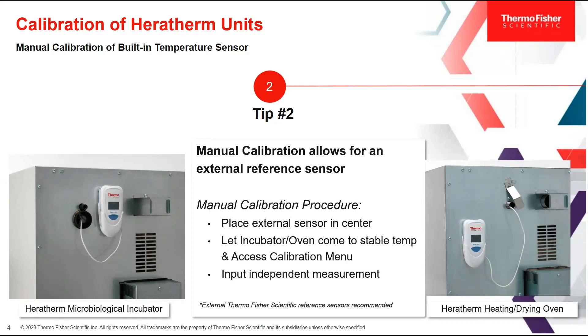We offer access ports on all of our units, usually on the back, that allow you to feed the sensor wire through so the sensor body is on the outside and you know exactly what temperature you're monitoring. Then we go through the same procedure: navigate to the LCD screen, go to the calibration menu, but instead of automatic, pick manual. Input the reference temperature and the unit will calibrate to that setting. If you're concerned about equilibration time, utilize that overnight window so you're not wasting valuable lab time.